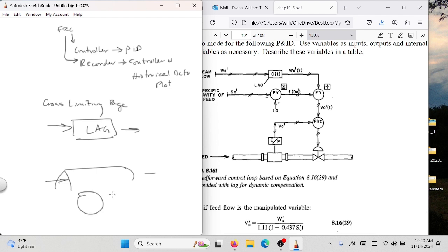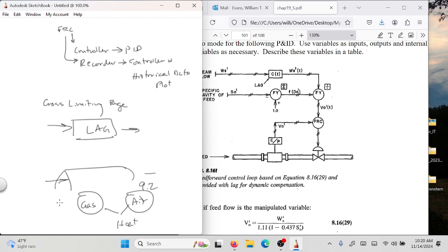In the cross-limiting context — you have a valve for gas and a valve for air. Combined with a match, they form heat. How much of each do you put in? About 9.1 to 9.2 parts of air to one part of gas to get a clean burn. More than that is lean. Less than that is rich. You want to maintain that ratio. In steel and glass furnaces above about 2100 degrees Fahrenheit, if you throw a little more gas or air in, the furnace is hot enough to handle it.